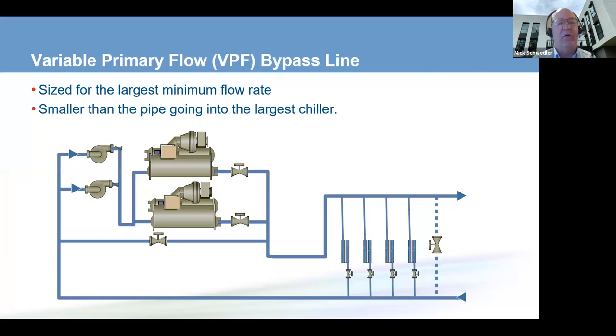Now let's go on to a variable primary flow system. In a variable primary flow system, the bypass line is differently sized. And that's because now it doesn't have to be sized for 110% of the largest chiller's flow rate. It only needs to be sized for the largest minimum flow rate. Usually that's the minimum flow rate of the largest chiller, but depending on the chillers in the plant, it's the largest minimum flow rate.